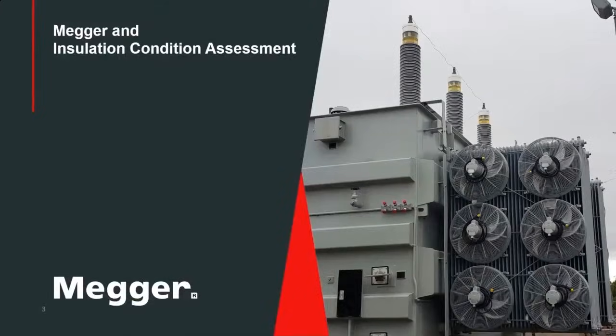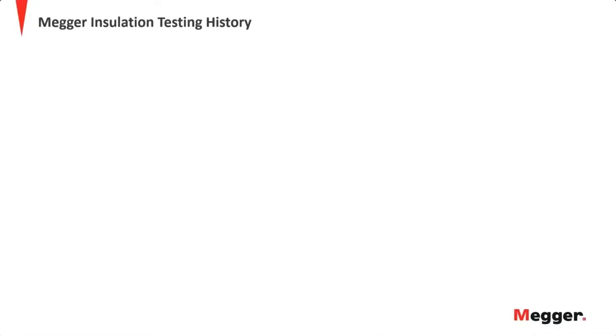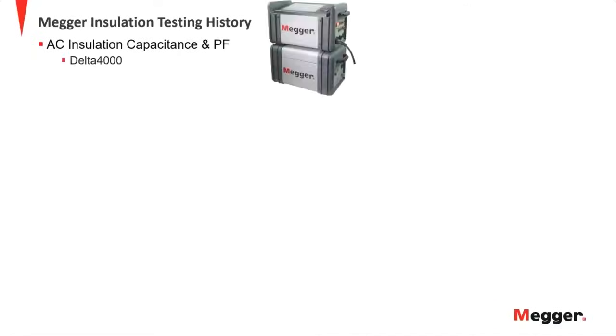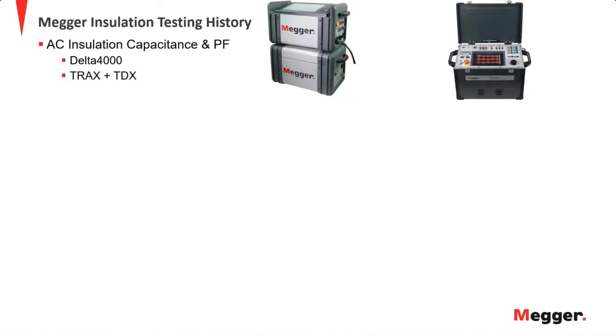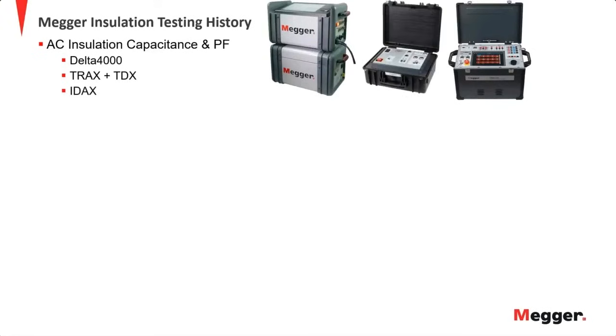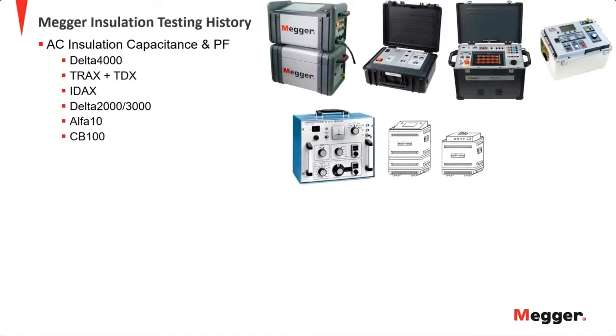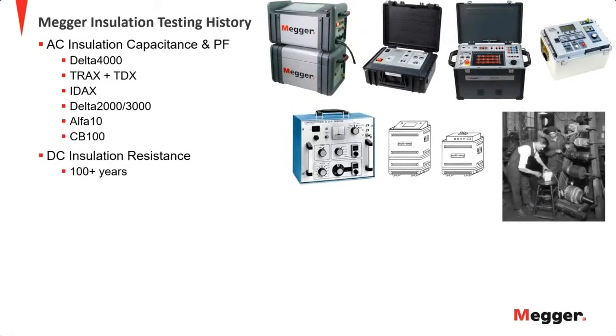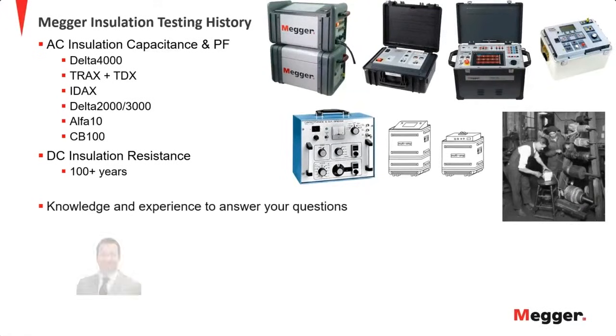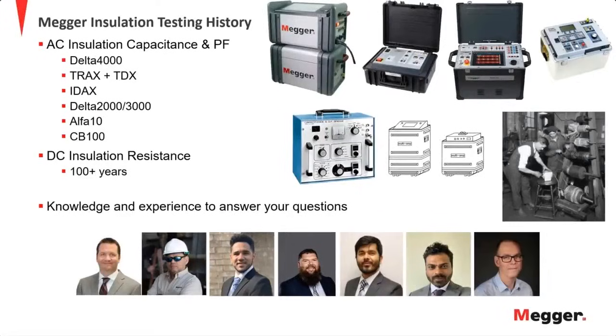So first, let's take a look at Megger and its long history with respect to insulation condition assessment of transformers. Starting with what we have out today. For AC insulation, capacitance, and power factor, we have the Delta 4000, the standalone insulation power factor test set. We also have the Trax plus TDX. This will be your multifunction substation tester that has a tan delta add-on. We also have the IDAX, which is our dielectric frequency response test set, which I'll talk a little bit about in later slides. Before that, we did have the Delta 2000 and 3000 preceded by the Alfa10, and we also had the CB100. And of course, before that, what Megger is well known for is DC insulation resistance, which we've been doing for over 100 years. And why do I bring this up? It's to let you know that Megger has the knowledge and the experience to answer your insulation questions.